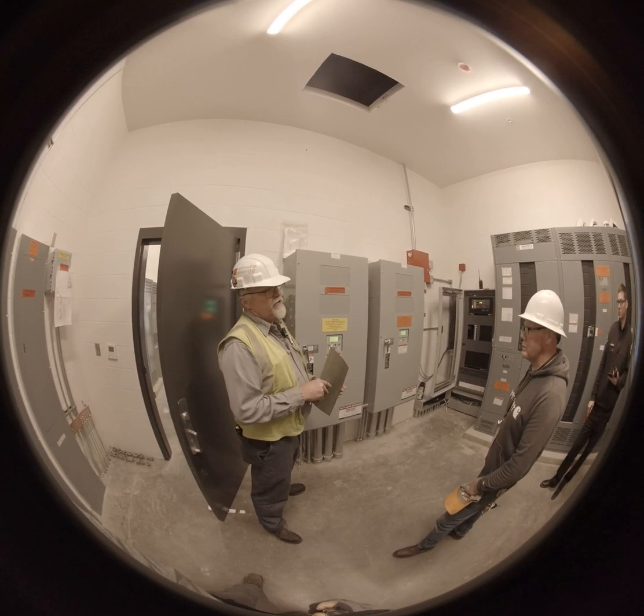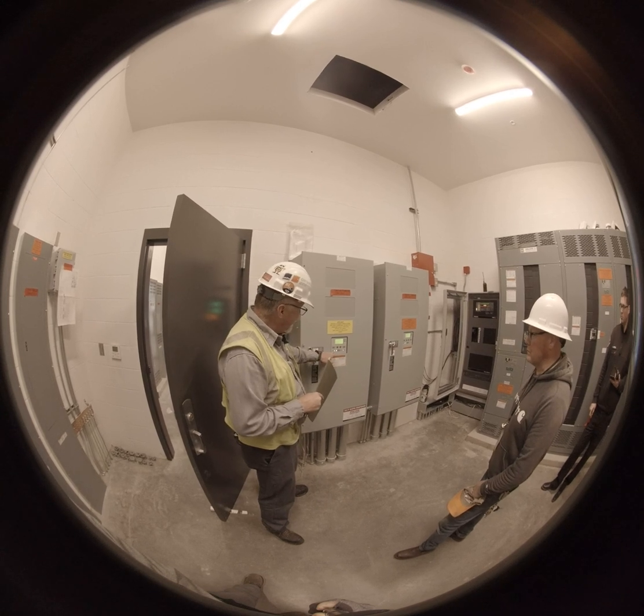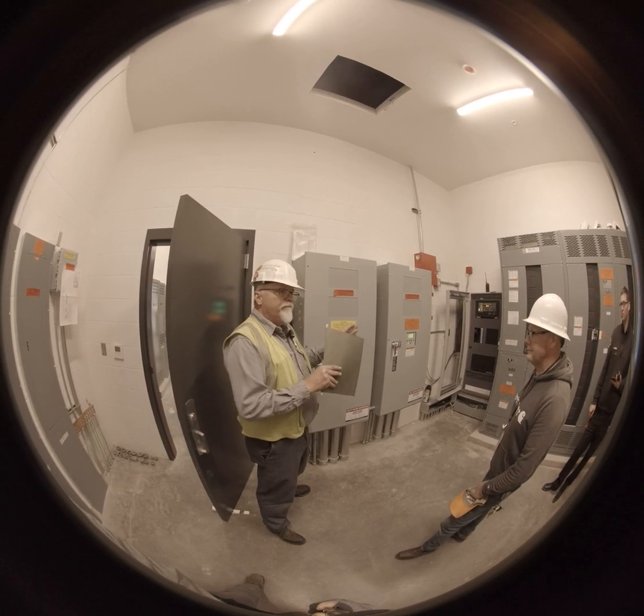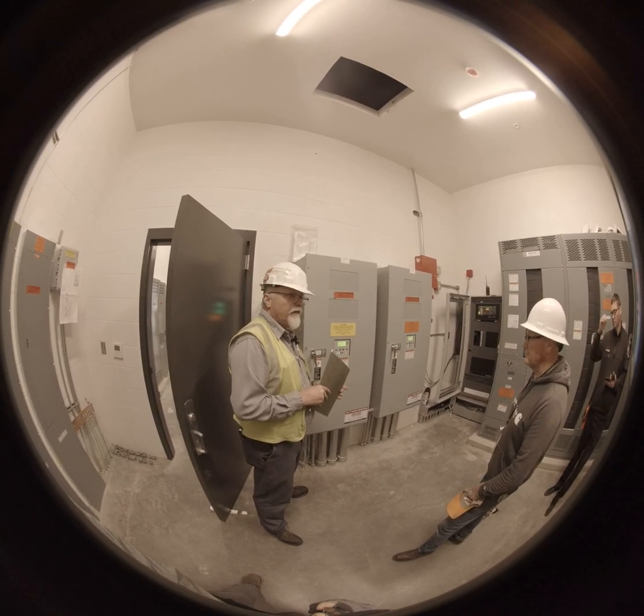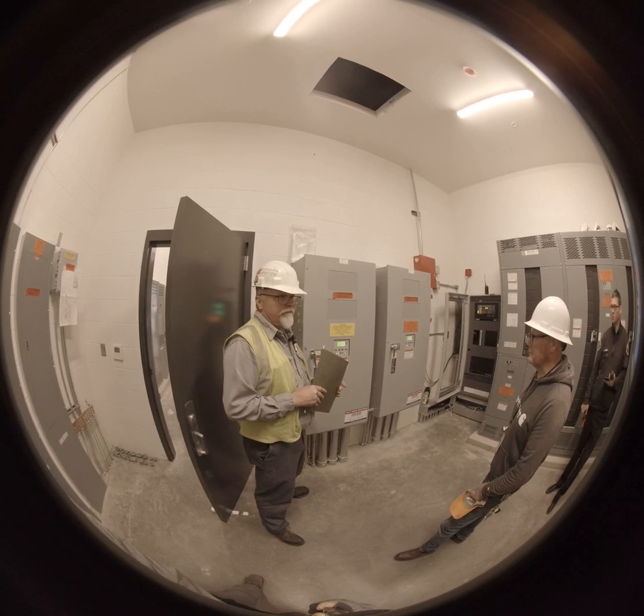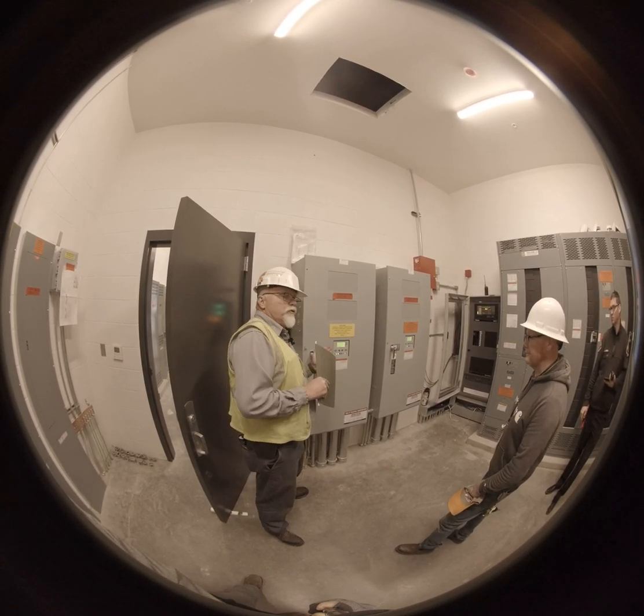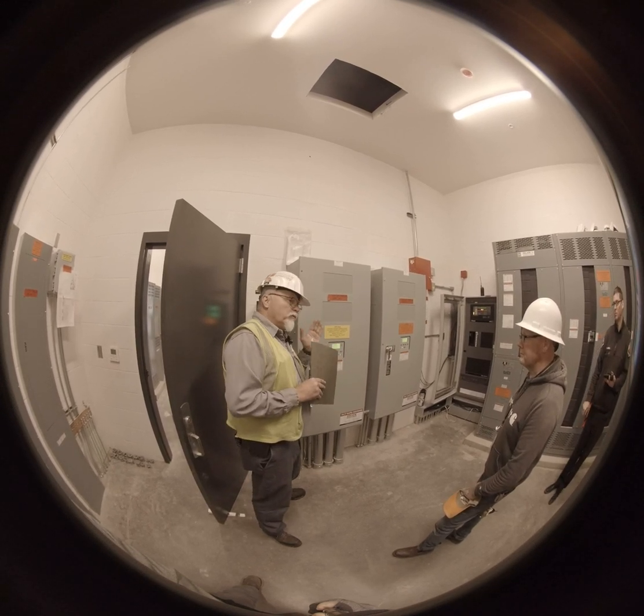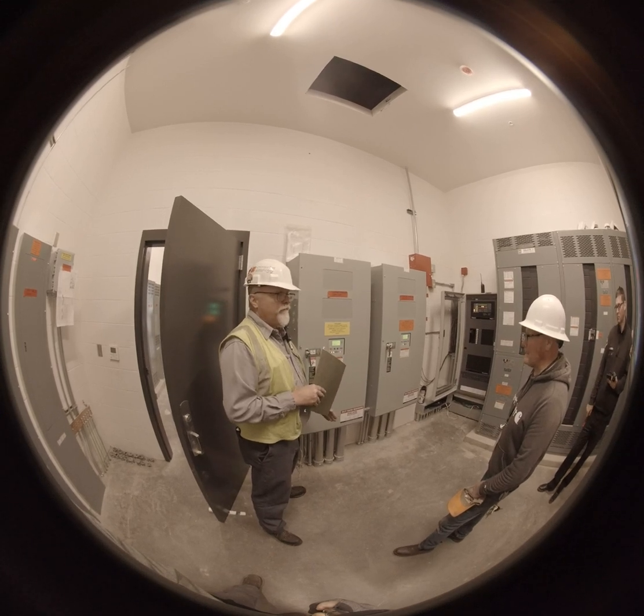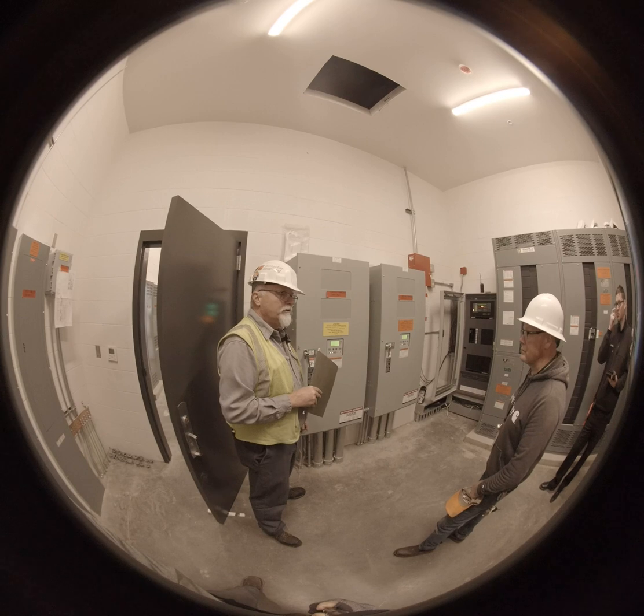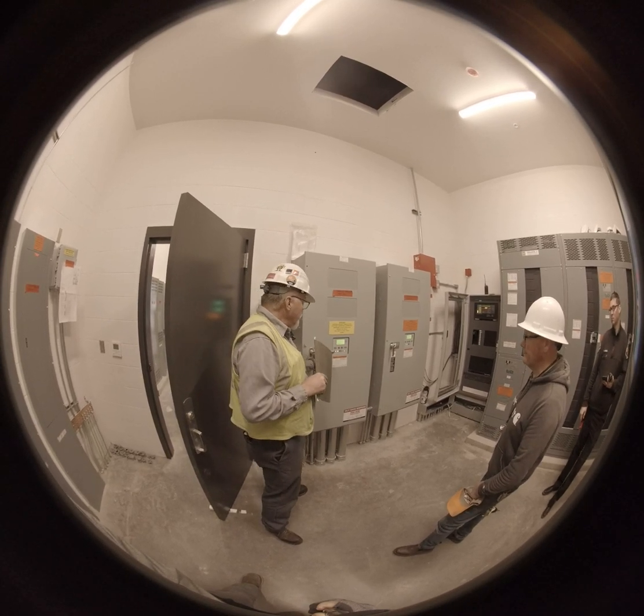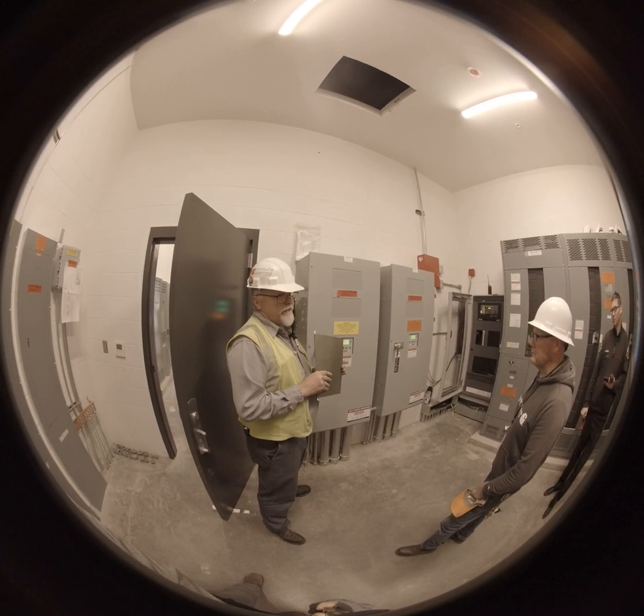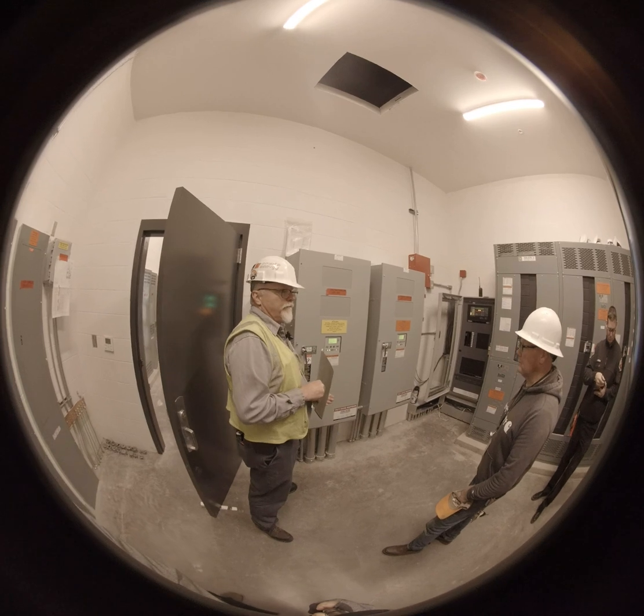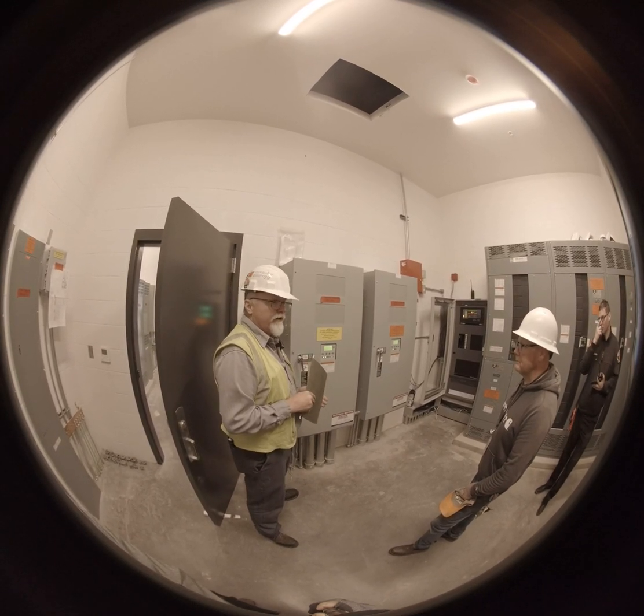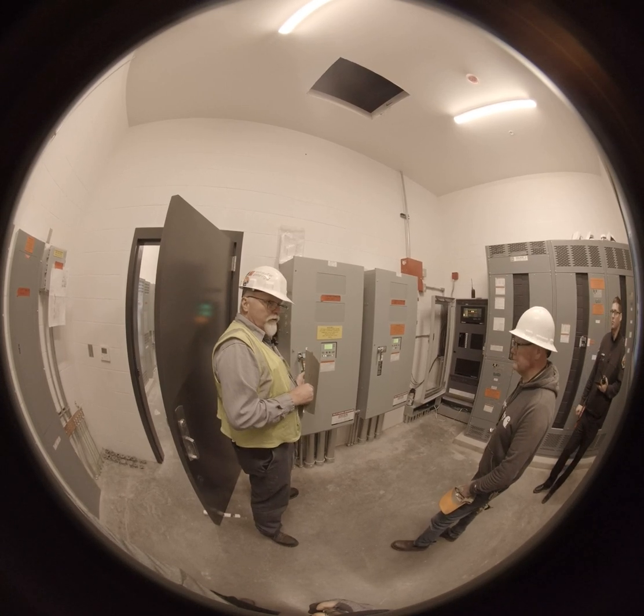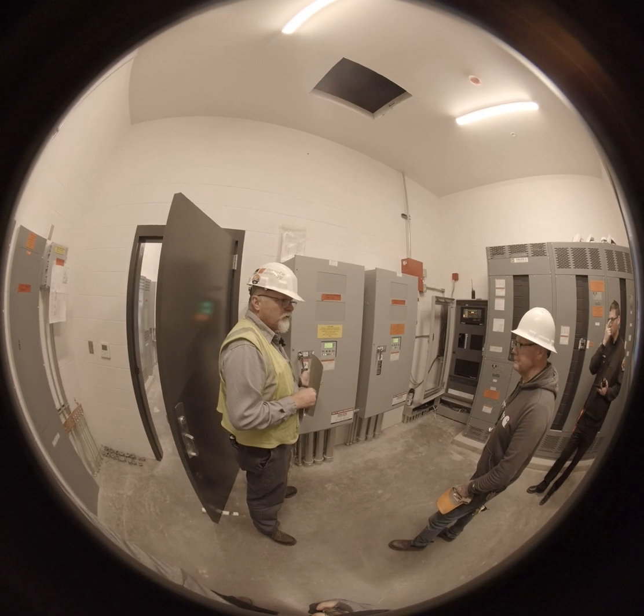It's going to sit there on secondary source until the green light over here on this side says, hey, this utility source is good, I'm going to allow you to go back. It's going to start a timer timing, and that's that 5-minute timer going back. If at any time during that duration the power blips down again, it's going to reset the timer. So if you've got unstable power, you've got your generators. Everybody else gets to take all this garbage going down the lines. You have a stable source. Once you have elapsed that full time delay without getting another dip on the power, then it's going to transfer back. This one will have, of course, the pre-signal going with the elevator again. Okay? Then it's going to go into cooldown mode. So, pretty straightforward.